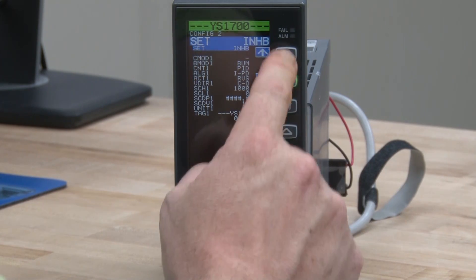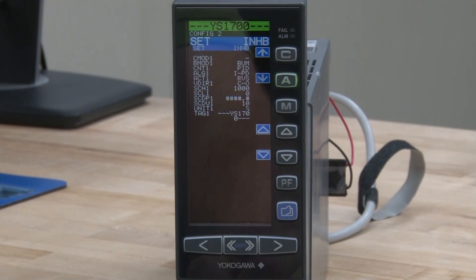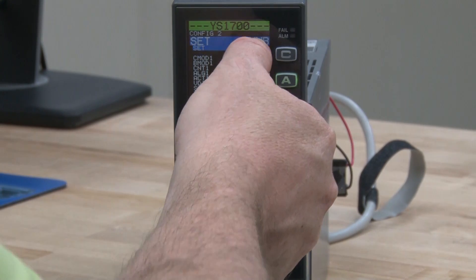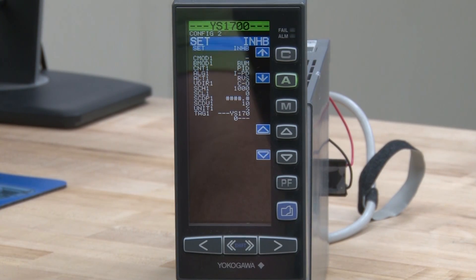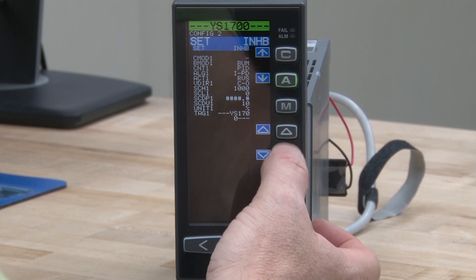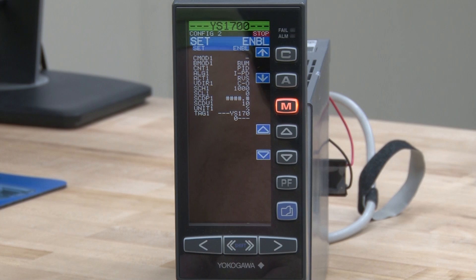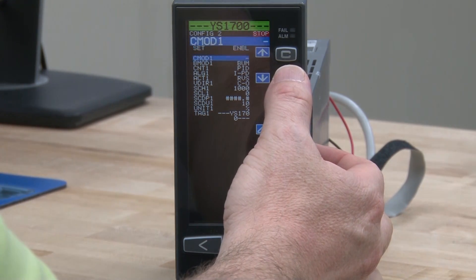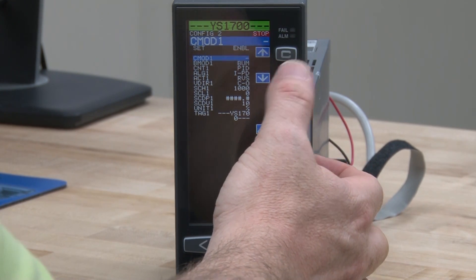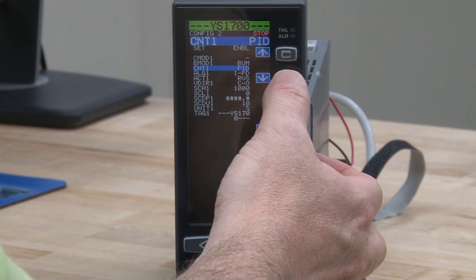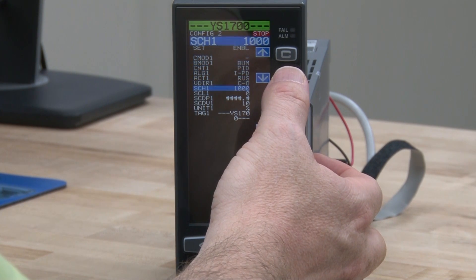We do that by pushing the down arrow button, which corresponds to the A key. We'll see that SET is currently highlighted and any changes right now are inhibited. To change that to enable, we push the physical up arrow key once, and you'll see the SET parameter changes to enable. Now we can hit the soft down arrow button, which is your A key, and move down to your scale high 1, SCH1.